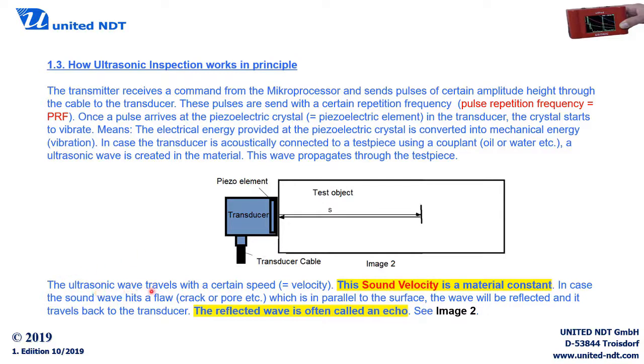The ultrasonic wave travels with a certain speed — this is the so-called sound velocity, a very common and important expression. Sound velocity is a material constant — shown on a yellow background, meaning important to understand. For example, if you have an unknown material, you can measure the sound velocity using an ultrasonic instrument, and from a table of sound velocities for different materials, you can identify what material it is. Ultrasonic inspection is actually used for that purpose as well.